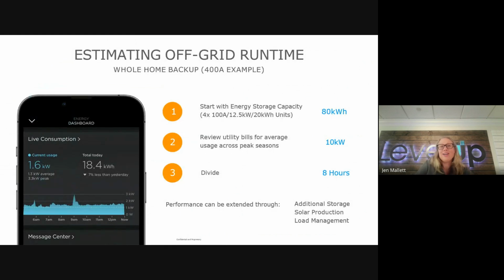So if we look at estimating off-grid runtime, this is a whole home backup example with 400 amp service. We're going to start with energy storage capacity. In this case, there are 4 inverters, 100 amps, and you're calculating to an 80 kilowatt number. You review your utility bills for average use across peak seasons. You're looking at 10 kilowatts, and then you take that and divide it and you get 8. So performance in this particular example can be extended through that base off-grid design by adding additional storage, adding solar production, and adding smart load management that enables you to shed loads during times when it really makes sense. So essentially what this gives you, this 8 hours, is your baseline for this particular design. And then you can add and extend performance with additional battery storage, solar production, and load management technology.